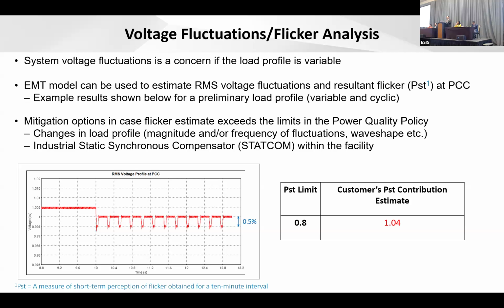You can see this load profile was very cyclic and repetitive. Once you know those voltage fluctuations, you can estimate flicker using the commonly used index, PST. In this case, we computed it at 1.04. Going back to our power quality policy, in addition to harmonics, we have limits for flicker. For a transmission system, the limit is 0.8. So our analysis shows it's exceeding the limit.